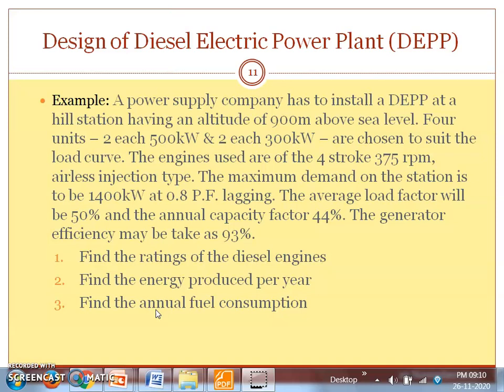The average load factor is taken as 50% and the annual capacity factor as 44%. The generator efficiency is taken as 93%. Note: do not confuse this with diesel engine efficiency — diesel engine efficiency is in the order of 43 to 46%, whereas the generator is an electrical device converting mechanical input to electrical output, giving around 93% efficiency.